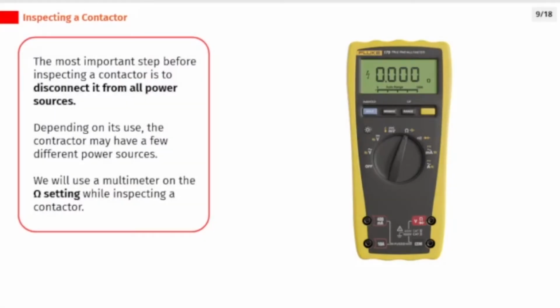The most important step before inspecting a contactor is to disconnect it from all power sources. Depending on its use, the contactor may have a few different power sources. We will use a multimeter on the ohm setting while inspecting a contactor.